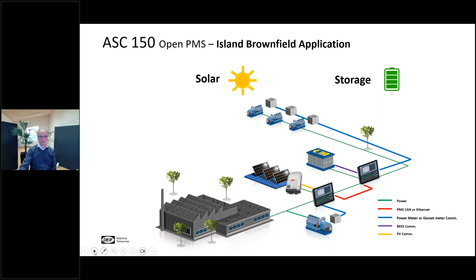The purpose is, of course, to maximize renewable production with the existing generators. You want to use this system when it's not in your scope to retrofit generator controllers on the existing generators, so you can still get the full benefit of a power management system. You have fuel saving, of course - we don't control the start stop of generators, we don't control priorities, things like this, but you still have the fuel saving, and we'll run the generators that the PLC system brings online on the minimum genset load in off-grid applications. So here, with the power management of the renewable sources, you still have the full cooperation for the PV production, charge cycles, discharge cycles, and curtailment of the PV.